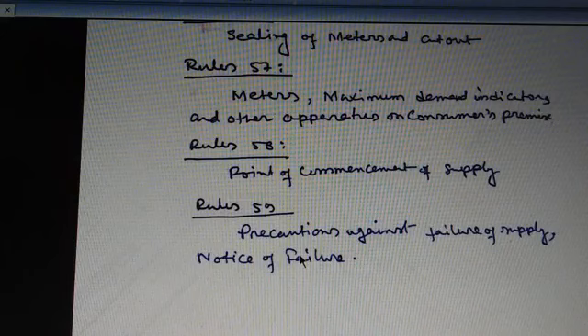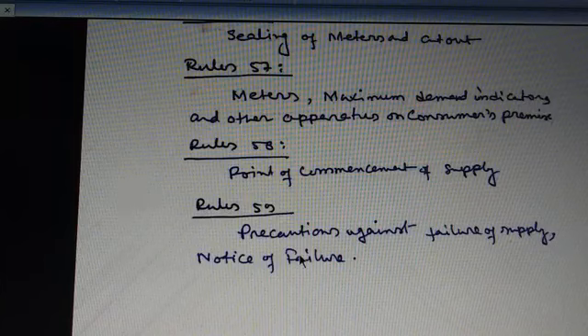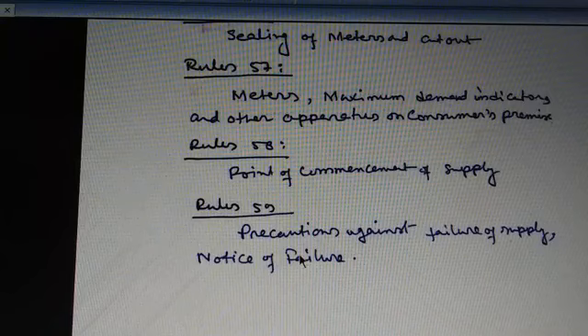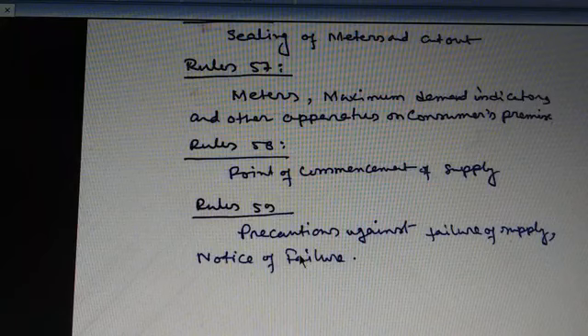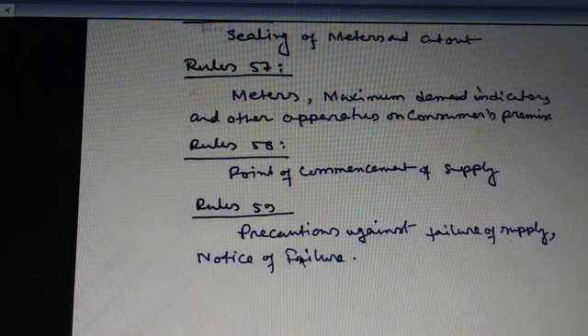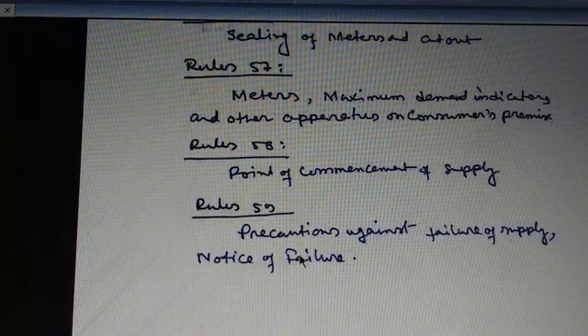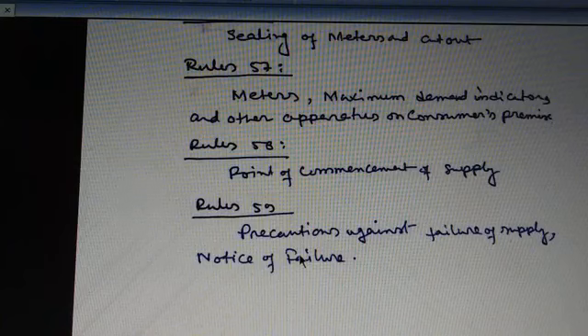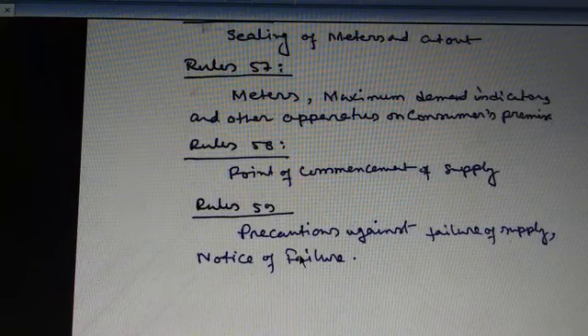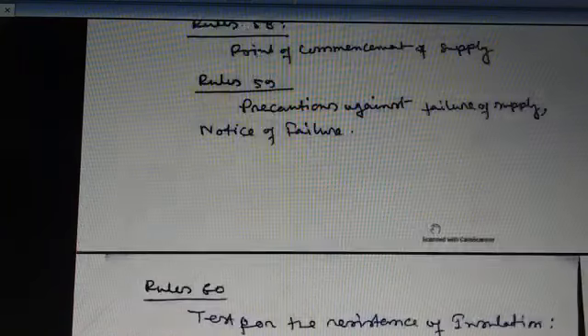Next, for the purpose of testing or for any other purposes connected with the efficient working of the undertaking, the supply of energy may be discontinued by the supplier for such period as may be necessary, subject to not less than 24 hours notice being given by the supplier to all classes of consumers specified by the inspector likely to be affected by such disconnections. So before disconnection of the supply, 24 hours notice must be given, and this is mandatory.